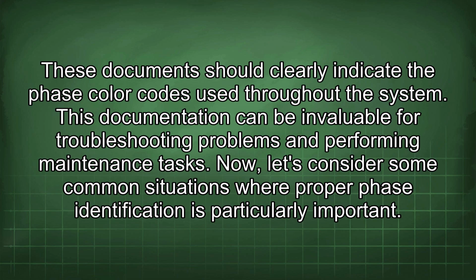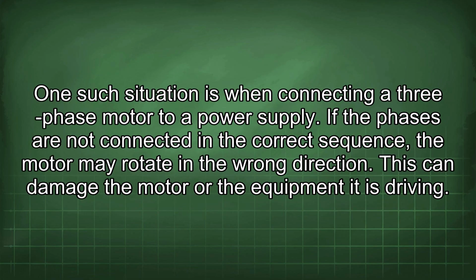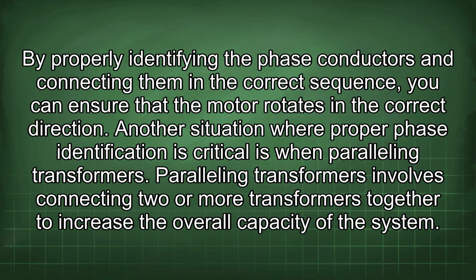Now, let's consider some common situations where proper phase identification is particularly important. One such situation is when connecting a three-phase motor to a power supply. If the phases are not connected in the correct sequence, the motor may rotate in the wrong direction. This can damage the motor or the equipment it is driving. By properly identifying the phase conductors and connecting them in the correct sequence, you can ensure that the motor rotates in the correct direction.